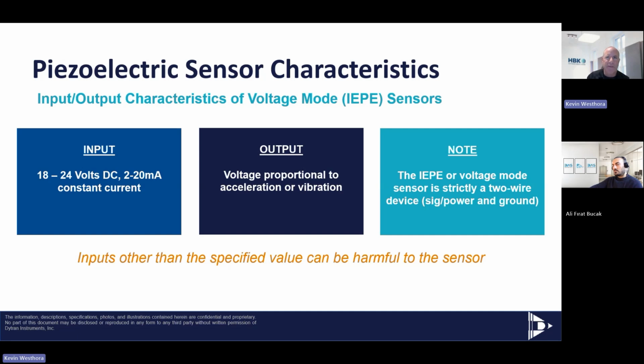Typically, the data acquisition system gives the sensor 4 milliamps, which is very adequate to power the sensor. The only time you would want more than 4 milliamps would be if you're running a very long cable to the sensor, let's say 100 meters. If you're doing a 100-meter cable, you would want to boost that up to 20 milliamps. Other than that, 4 milliamps is very adequate. The output is proportional to the acceleration. Like I mentioned, you get plus minus 5 volts at full scale G range for every IEPE accelerometer.